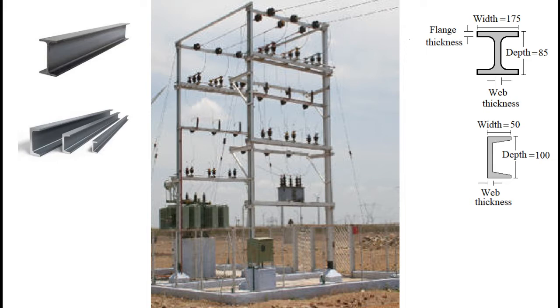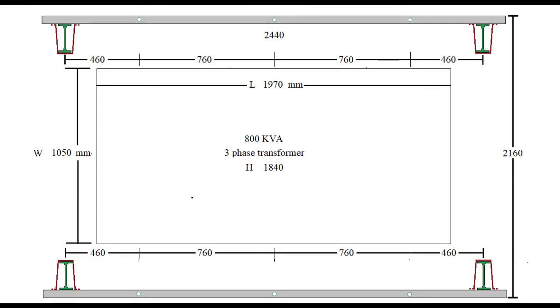We are selecting 4 I-section poles with 175 by 85 mm dimensions that have approximately 20 kilograms of weight per meter. Each pole will be 9 meters in length. These poles would be 1.5 meters inside the ground, and 7.5 meters would be the height above ground. It is expected to keep 760 mm of clearance between phases and 460 mm of clearance between poles and phase. We consider the pole to be at ground potential.